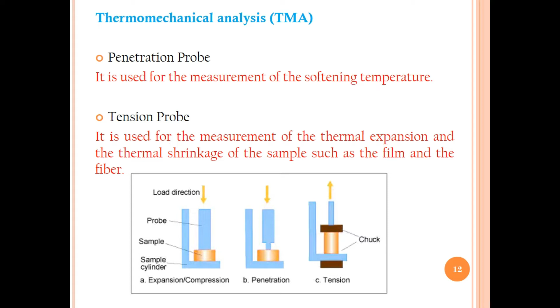Let's see about the instrumentation. The sample tube that is located in the center of the furnace is used to control the temperature and atmosphere. That is clearly shown in the block diagram. The probe is shown, the sample is placed, the furnace is for temperature control, and a thermocouple is for temperature sensing. The LVDT detector is the length, expansion or compression sensor, and the signal related to position is given to the recorder, and load is applied at the top of the instrument. This is the block diagram of TMA.